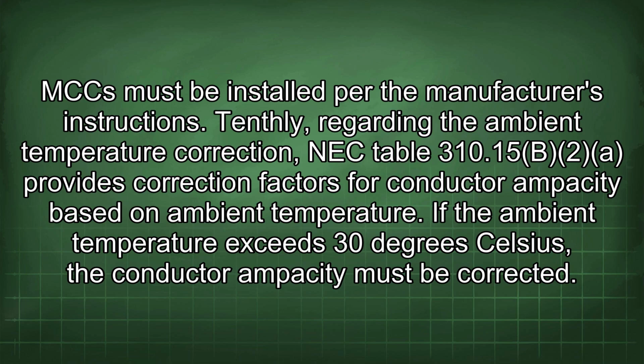Tenthly, regarding the ambient temperature correction, NEC Table 310.15(B)(2) provides correction factors for conductor ampacity based on ambient temperature. If the ambient temperature exceeds 30 degrees Celsius, the conductor ampacity must be corrected.